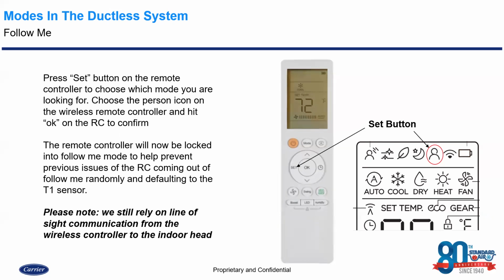So unlike the previous wireless remote controller, where we would hit Follow Me and sometimes fall in and out of it, this wireless controller locks into Follow Me mode to try to prevent that signal interference. However, we still rely on line-of-sight communication, because we are reading temperature with a wireless handheld remote controller. So it's important to keep that wireless controller within visual distance of the indoor unit with nothing blocking it. Okay, now if for some odd reason the Follow Me mode just doesn't communicate, or it does default back, the default sensing method on this unit is going to be like any other unit, the T1 or your return air sensor.